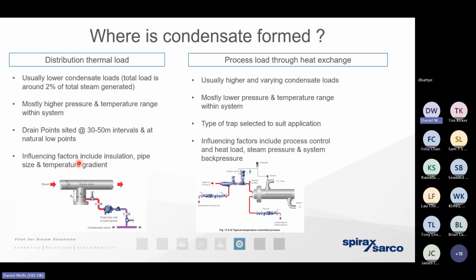That's the information that we size the steam traps on. The rest of the condensate, well, that's going to exist at the point of use, at the heat exchanger. So it's a significantly greater mass of condensate that we need to remove. And that's a good thing, because that's where we want the steam to condense. But we need to apply that same rule of thumb, that warming up load, because a heat exchanger, it's a huge chunk of metal. If we're warming a heat exchanger, a process up first thing in the morning, more and more of the steam is going to condense as it warms up the heat exchanger itself before it imparts any heat energy to the process. So we need to get that condensate away really, really quickly, because condensate as a liquid, we know it's the same temperature as the steam. It's just got far, far less energy in it.